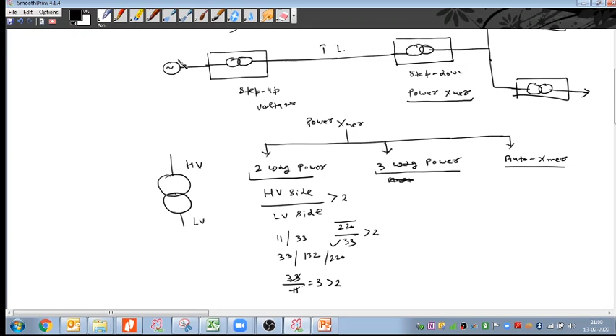If there is 220 by 33, 33 kilovolts generated, then step up to 220 kilovolts, this ratio is again greater than 2, right? So whenever we are talking about the generating substation transformer type, the substation that is placed near the generator, that voltage ratio will always be higher than 2. They always prefer to use a two winding transformer. Whenever we have two power generating sources, suppose we have a combined cycle power plant, we have the gas, we have the steam, or we have more than two power sources, in that case we have a three winding or five winding or more than two winding power transformer.